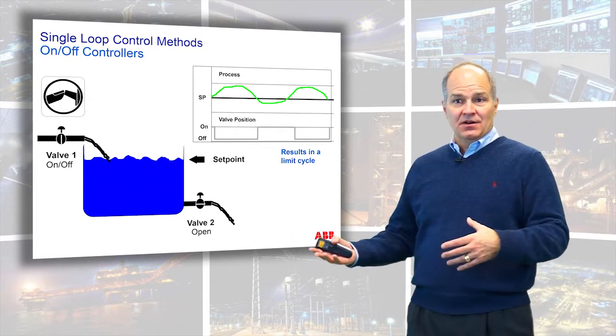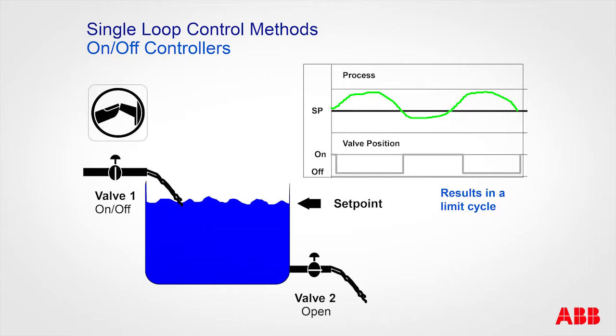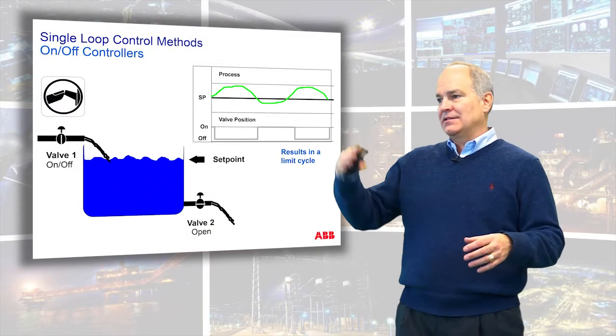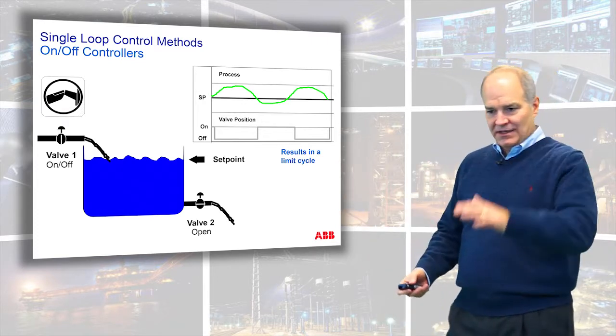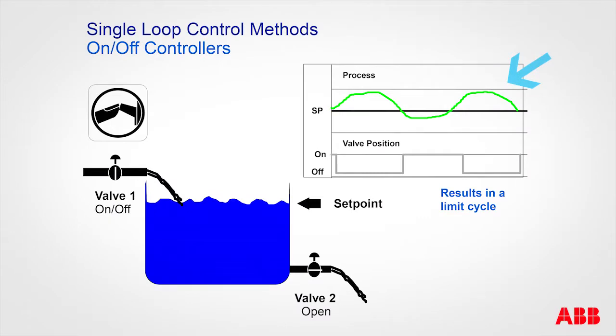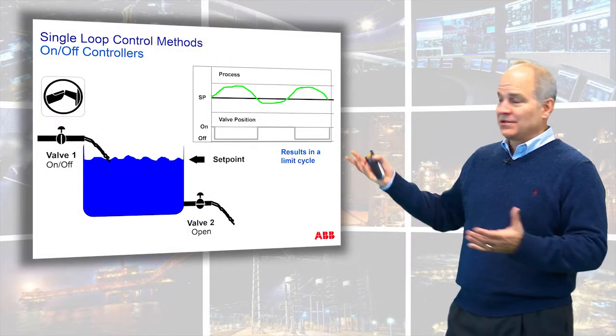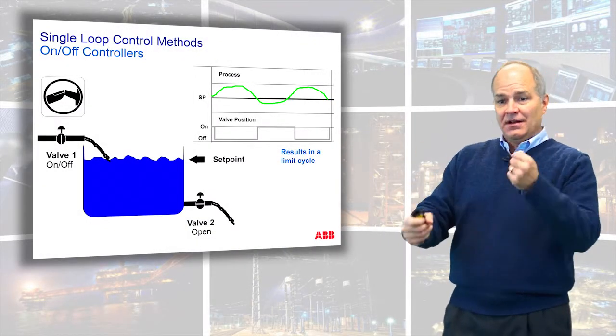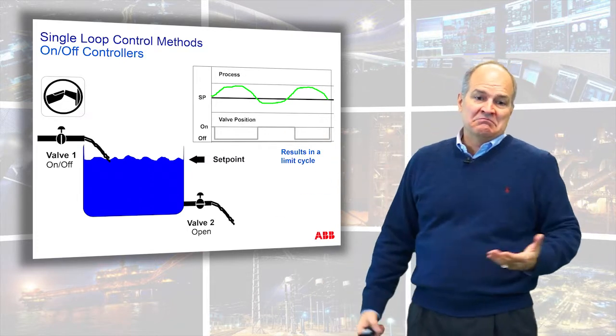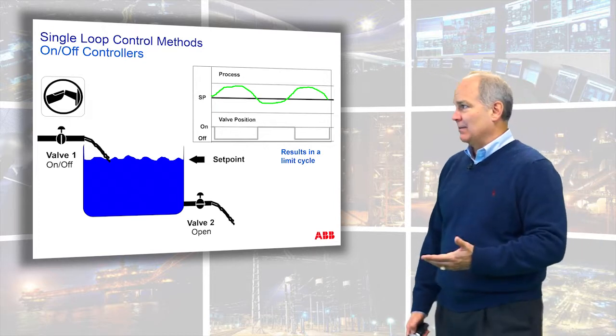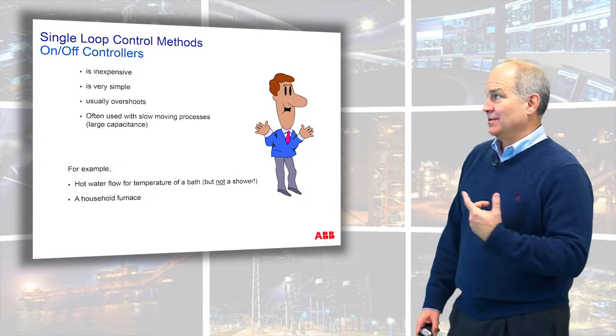Here I'm showing an example with a large tank — a large vessel that doesn't move very fast — so to get anything to happen you have to turn the actuation device on 100%. It starts up and goes, but what you end up with is always an oscillation up and down. Maybe that's good enough. A lot of houses work this way: your furnace turns on, then off, then on, so the room temperature oscillates.